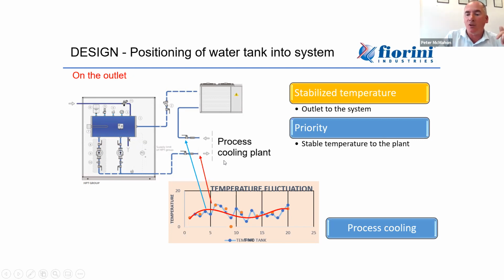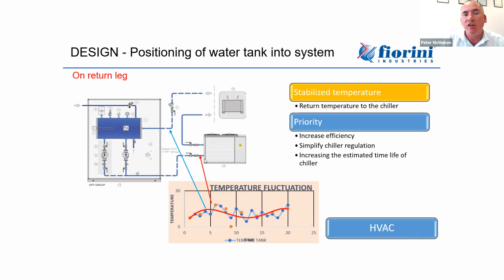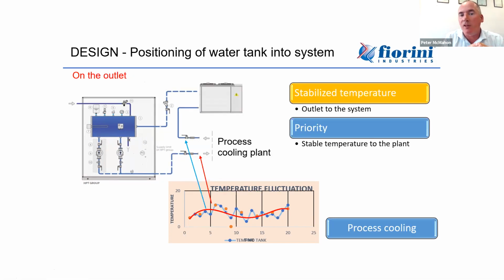So more often than not, if you are going to put it in series with your loop, we will suggest putting it on the return leg here to your heat pump, because we know that's better for your equipment and for the efficiency, the operation of your equipment. Like I said, some people say, no, I need to have a very, very stable temperature and I want to have it on the outlet, in which case that's the other option that's available to you.